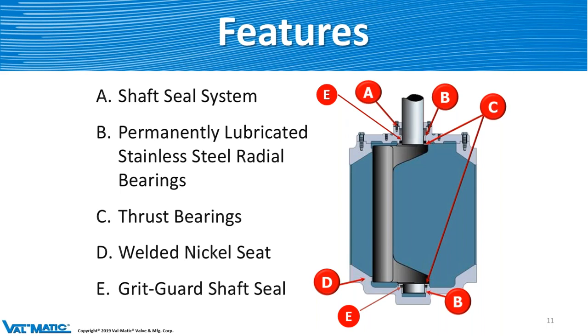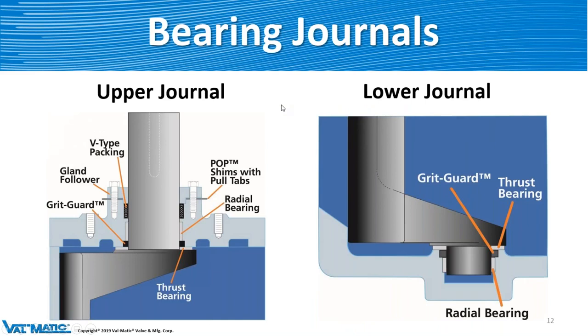The features include the shaft seal system — that's a V-packing, permanently lubricated bearings, thrust bearings, nickel weld, and a Grit-Guard. Let's go over the bearing journals in a bit more detail. On the upper journal, you have your V-type packing, gland follower, shims, and bolts to adjust that packing — you can tighten it if need be. You have your bearings, then the Grit-Guard and thrust bearing. That Grit-Guard helps keep all the junk and debris from getting up into the bearing and packing area, which is very important.